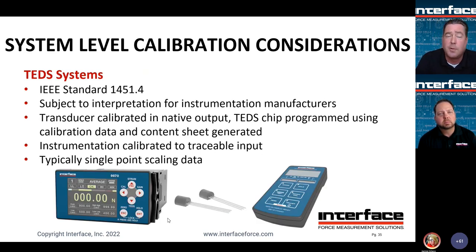TEDS is also a whole different animal. The IEEE standard for TEDS is 1451.4. It has some defined characteristics about it. However, a lot of times it is very subject to interpretation for how that scaling data is used by different instrumentation manufacturers. And as a result, you get kind of a varied approach from each. So often the way it looks for us is the transducer is calibrated in its native output. This could be voltage, it could be a current output, it could be millivolts per volt, and then the TEDS chip is programmed using said calibration data, and a TEDS data sheet is provided with the transducer to reflect how that chip is programmed. Typically, the instrumentation is then calibrated to a traceable input.